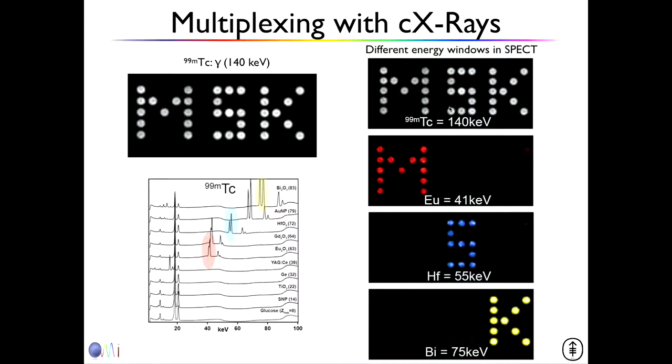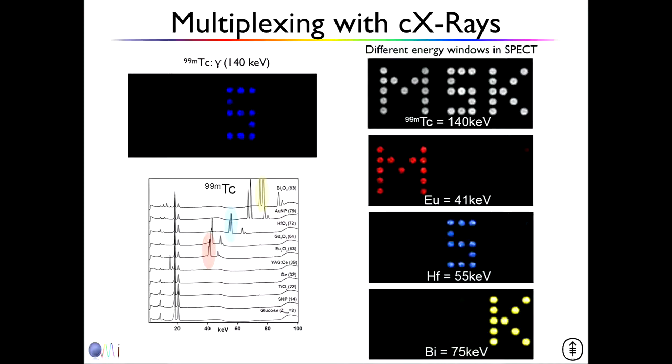And so we did MSK, Memorial Sloan Kettering Cancer Center. We didn't do the CC, and looked at different energy windows. The problem we had, to be quite honest, is that to get really nice energy resolution with the scanner we had was quite difficult. And also to get a good calibration, because of course all these spectra and wavelengths are not even in any of the software you get from the vendors, so we had to create them on our own. Newer scanners, by the way, will have a much nicer energy resolution, so you can probably get much better results.